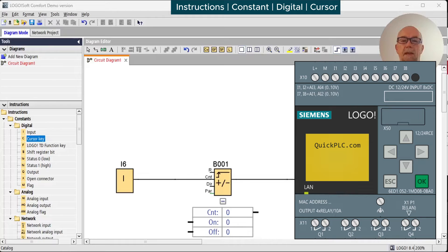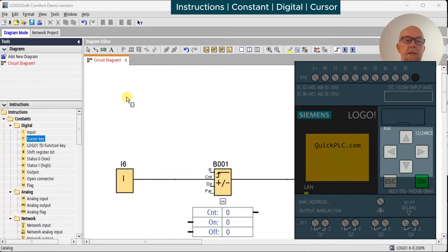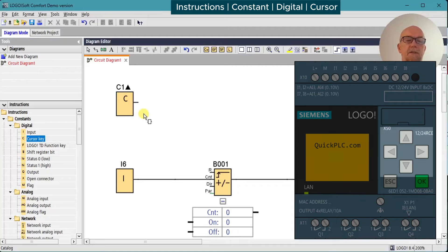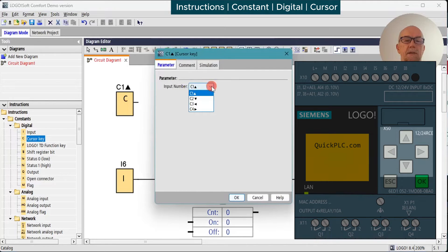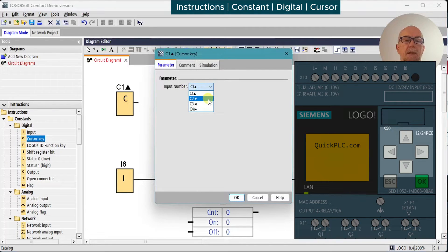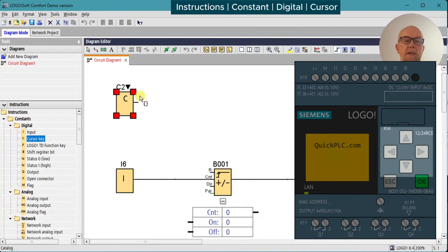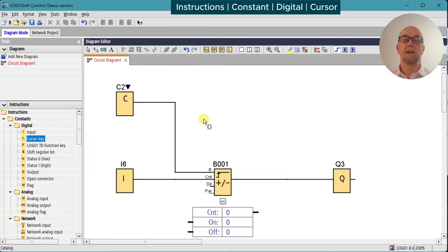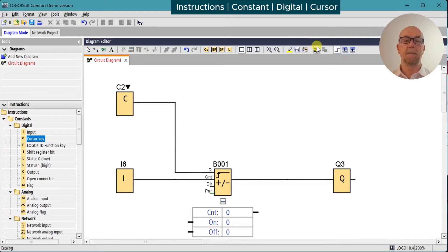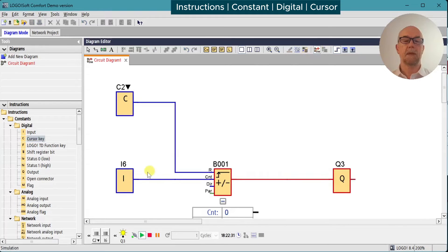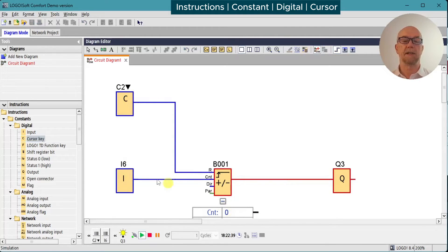A nice feature of the LOGO is the use of the cursor keys, which give us effectively an extra four inputs to the PLC. We can configure these to use the up key, the down key, left key, and the right key. So we're going to set our counter reset to use the down key. Since the cursor keys are already used for menu navigation, you press escape plus the cursor key to make it active. We'll run our simulator here, and we'll count up a few cycles, hit the cursor key, and observe that the counter resets to zero.